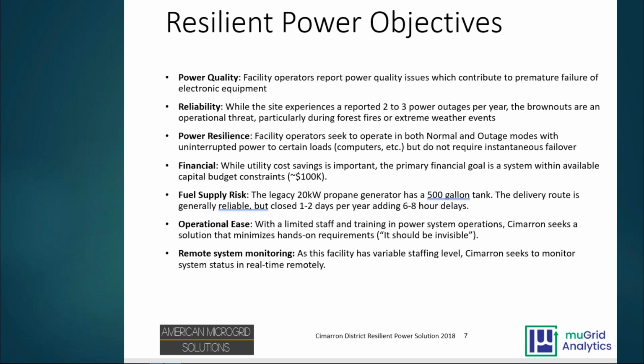Fuel supply: the site runs on propane. It has used a propane-powered generator, but we were going to filter the generator output through the inverter system to clean up the power out of the generator. That was a requirement to improve power quality.